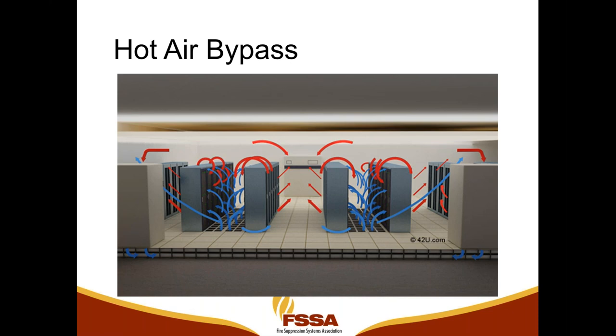Essentially, when you've got a lot of hot air bypass happening in your data center, the servers or the IT equipment at the top of your racks will be the ones that tend to overheat. And when IT equipment overheats, the safety built into it automatically shuts down a lot of that equipment. And so you can have unwanted stoppage of that IT equipment. And so that's what we're trying to avoid with aisle containment.